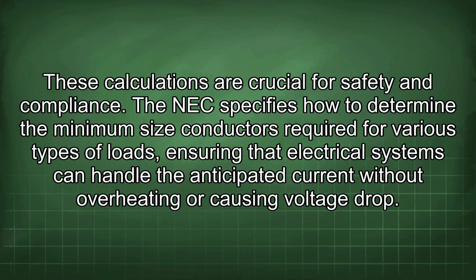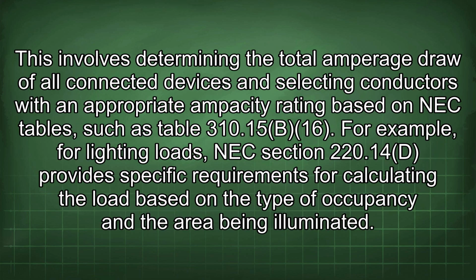The NEC specifies how to determine the minimum size conductors required for various types of loads, ensuring that electrical systems can handle the anticipated current without overheating or causing voltage drop. This involves determining the total amperage draw of all connected devices and selecting conductors with an appropriate ampacity rating based on NEC tables such as Table 310.15(B)(16).